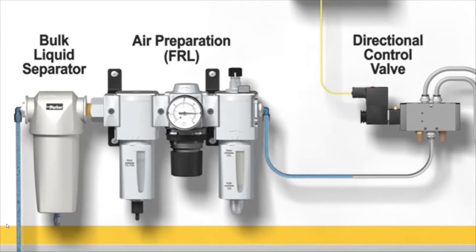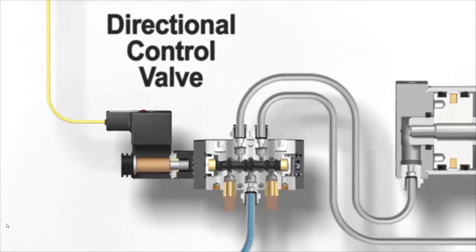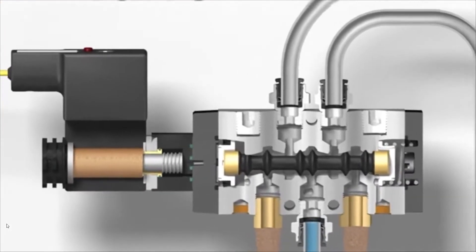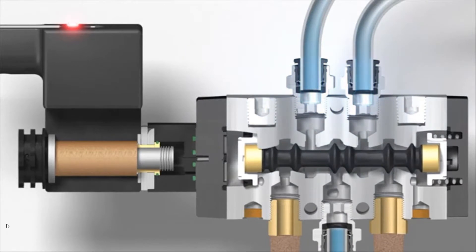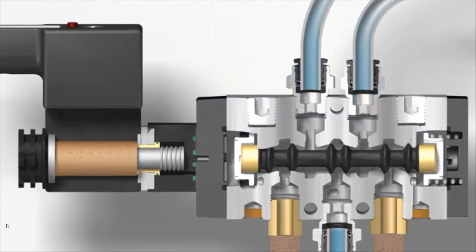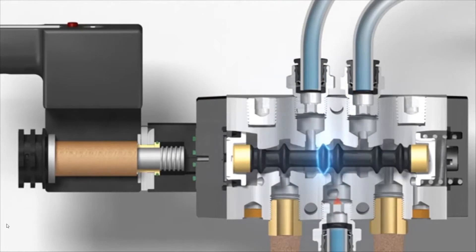A directional control valve is used to achieve this task. This directional control valve has a series of internal pathways that can connect the air coming into the inlet port with one of two avenues to leave the valve, called working ports. Depending on the position of the moving element, which is typically called a spool, the air will be blocked from traveling down one pathway and allowed to travel down the other.